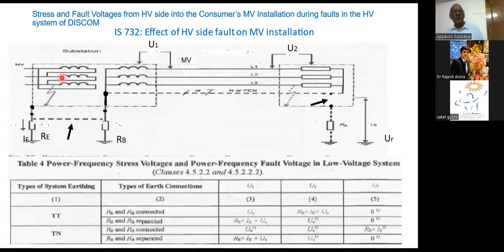This is the thing. But what will happen in field reality? You actually can't have a separated system, because these are all placed in a constrained location. You can see the distribution transformers are pole mounted, and all that body and neutral, everything is located within the shortest distance. Its electrode will have its own influence on the other electrode.